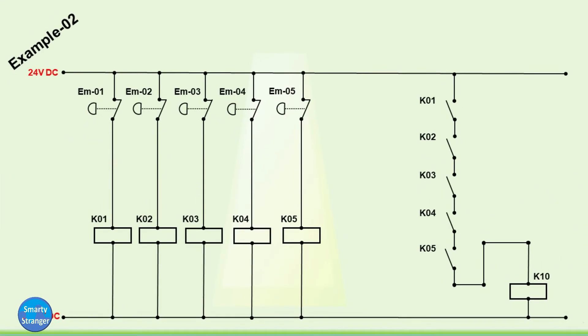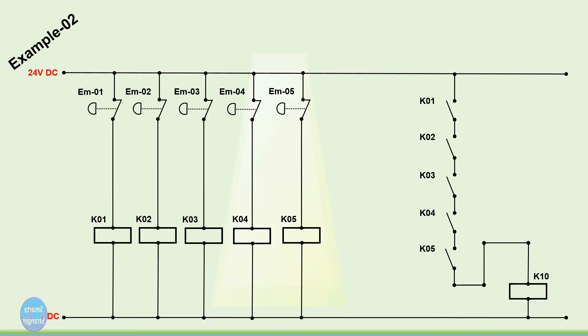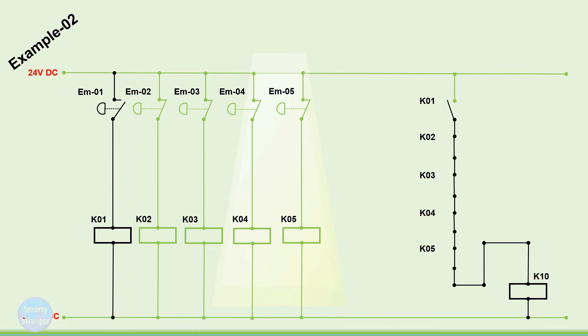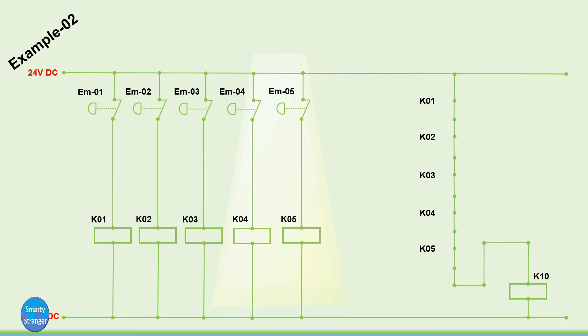Let us consider another example, example 02. Here we have an emergency circuit. Five emergencies are installed in different areas of the field to break the connection. These emergencies are connected with 5 relays separately, and contacts of these emergencies are used in series to operate relay K-10. Contacts of K-10 could be used in other outputs for safety purposes. In normal condition, when the circuit is energized, all relays are operating and their contacts are energizing relay K-10 — this is the healthy condition. When an operator triggers an emergency in any area, its relay de-energizes, breaking the series connection of K-10, which also de-energizes. When K-10 de-energizes, all program outputs stop. When the operator normalizes the emergency after inspection, the circuit becomes healthy again.